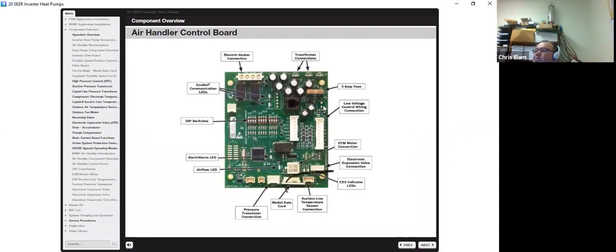This is kind of a picture of the board here. So you've got your electrical heater connections here, your transformer, your SEC1, 2, has a built-in 5-amp fuse. Do not ever plug anything into this, what appears to be a phone jack. You have your low voltage connection terminals here and here. So you'll actually have 2 sets. This is what they call your legacy controls. This is your normal 24-volt wiring over here. Over here you have your E1, E2. You also have 2 auxiliary options, and you have 2 dry contact terminals.